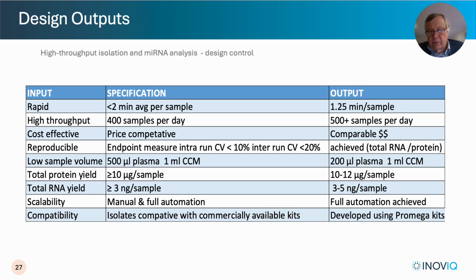In terms of the design outputs, the performance of the fully automated EV isolation system, we are seeing that the design outputs satisfy the design inputs in that the average sample processing time is less than 2 minutes. We have capacity of more than 500 samples per day, and it will operate on low volumes of plasma and cell-conditioned medium, delivering total protein yields and RNA yields sufficient for downstream analysis.